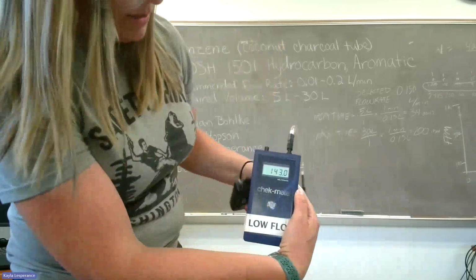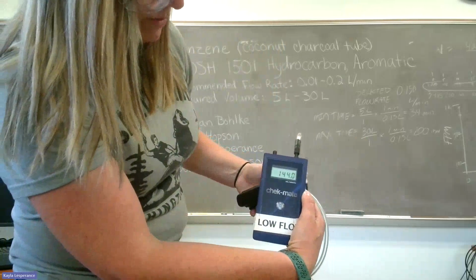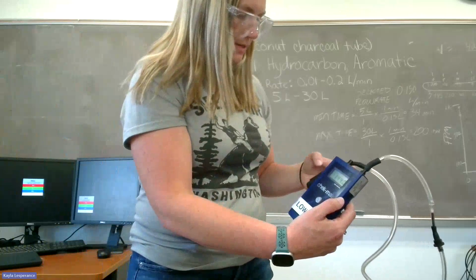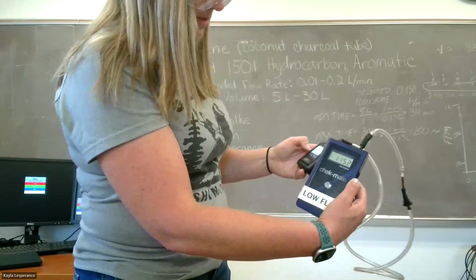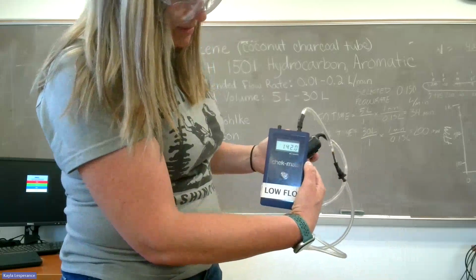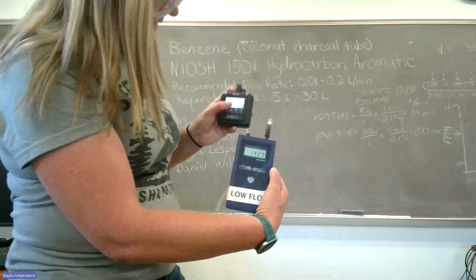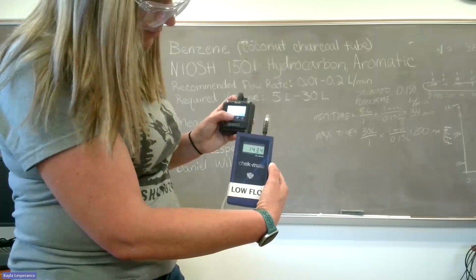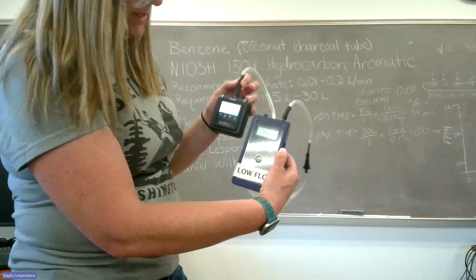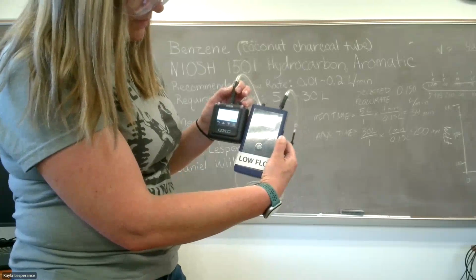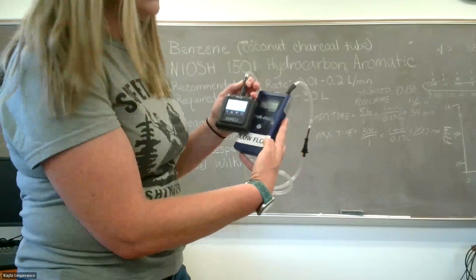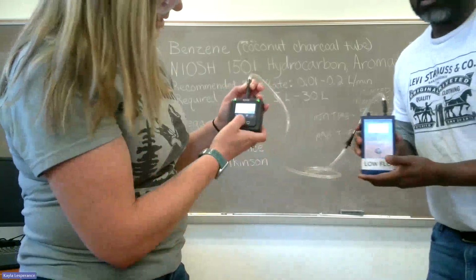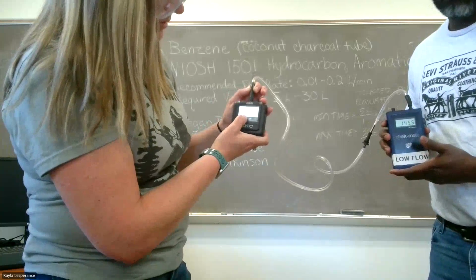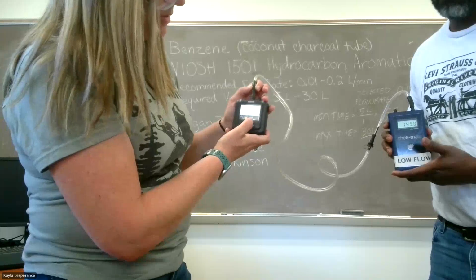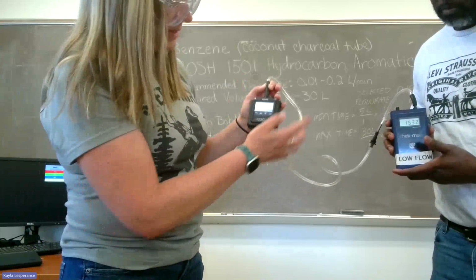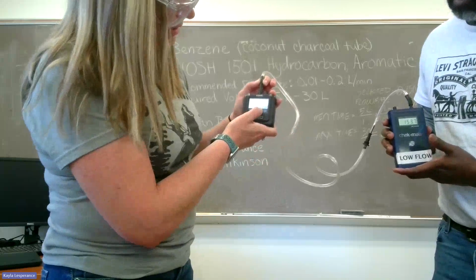And you can see that our flow rate is at 144. So we would go ahead and adjust that. So we're going to wait for that to give us, so we can adjust our flow with the up and down arrows in the calibration menu. So we're at 143. Oops. And you want to make sure your tubing doesn't kink. You get a good flow rate. So Jeff, can I get you to hold this for a second? So we can adjust the flow up. What's happening is the flow is not going through the media as quickly because the media is creating resistance inside the tube. So we got up a little bit high.